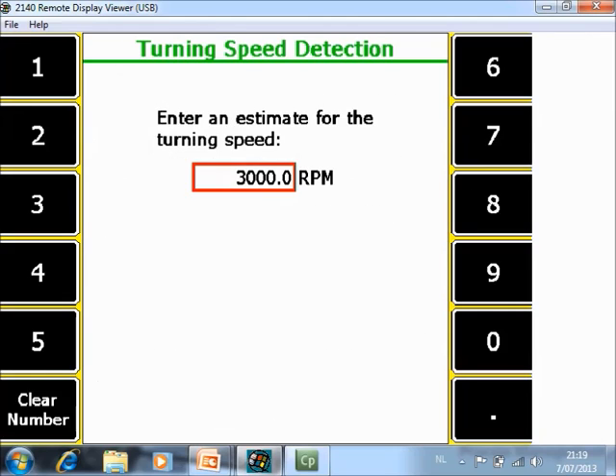Push Start and now the data collector will ask you for an estimation of the speed. So if you believe that your machine is running in the neighborhood of 3000 RPM, enter 3000 RPM. I will now start the machine and collect a quick spectrum. In the spectrum it will look for an imbalance value in the neighborhood of 50 Hz.